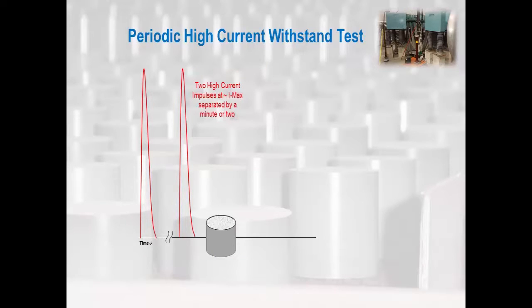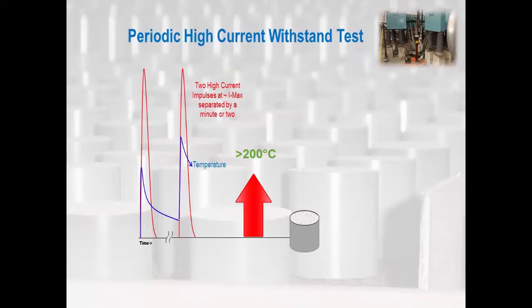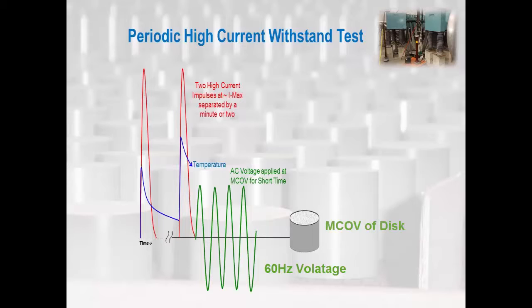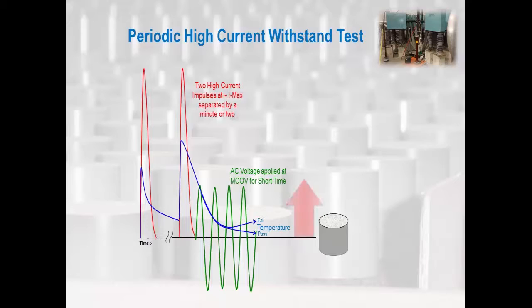During these 2 impulses, the temperature of the disc increases to well over 200 degrees C. Immediately following the impulses, a 60 Hz voltage is usually applied at a level near the disc's MCOV. How the disc responds to the impulses and AC voltage is critical. If it cools and then starts to increase in temperature, we know the disc is damaged internally.